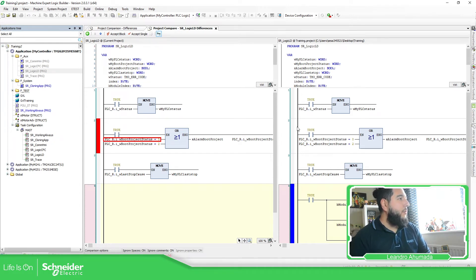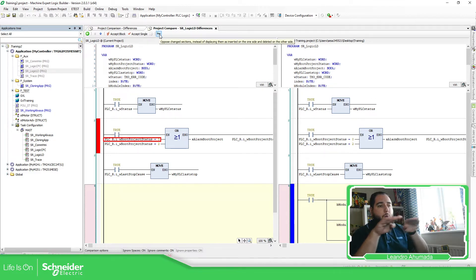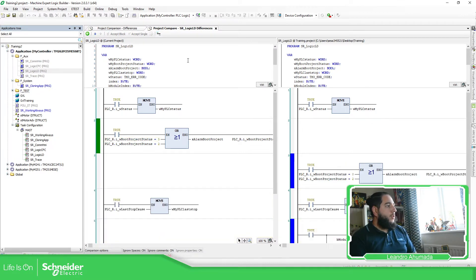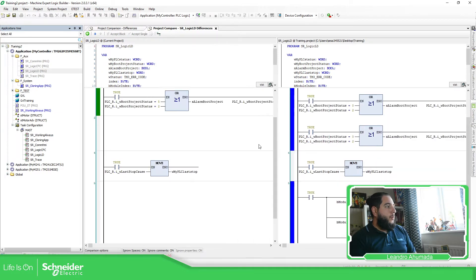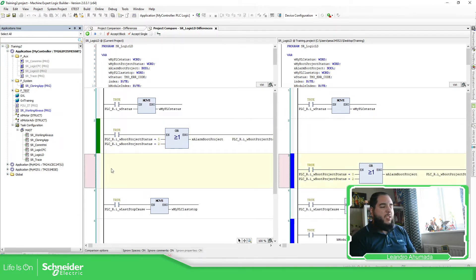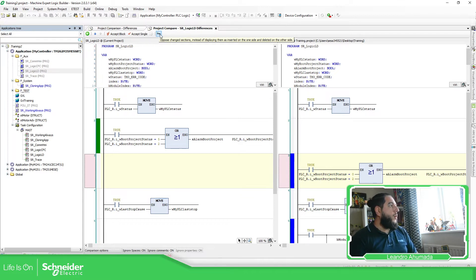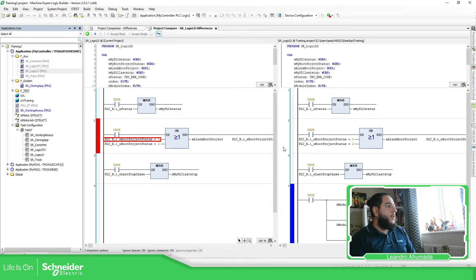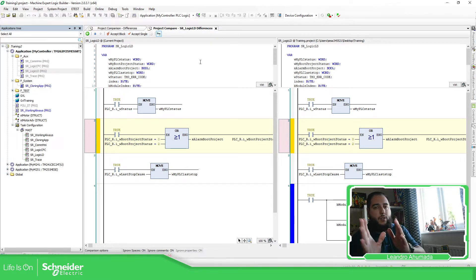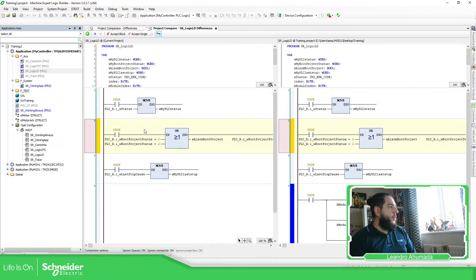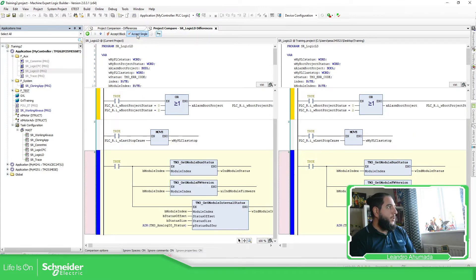Another thing we can do is change the visualization. You can select this option, which will try to compare all elements on the same rung. If I uncheck this, it separates all the differences, which allows you to check further on new items. For example, here it adds a new rung just to make the comparison. And if you want, you can move the code to one side in case you have additional code. So I'm going to uncheck this part to make the real comparison, and then you can move code from one part to the other. Accept single — it moves from the original code to the new one. Then here, if you want, you can accept the code.